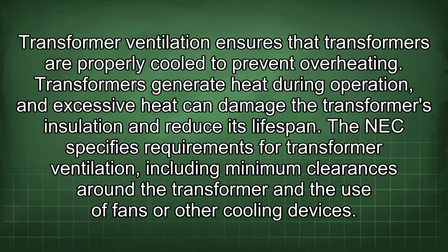Transformer ventilation ensures that transformers are properly cooled to prevent overheating. Transformers generate heat during operation, and excessive heat can damage the transformer's insulation and reduce its lifespan.